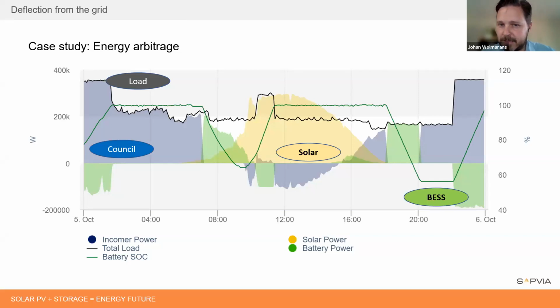And then during the middle of the day, we charge again using solar. And then in the afternoon from 6 to 8, we discharge from battery energy storage again. And so the cycle repeats itself. And obviously the cost differential between your peak tariff and your off-peak tariff, and in this case, your solar LCOE, gives you that saving that you realize for every kilowatt hour that you arbitrage.